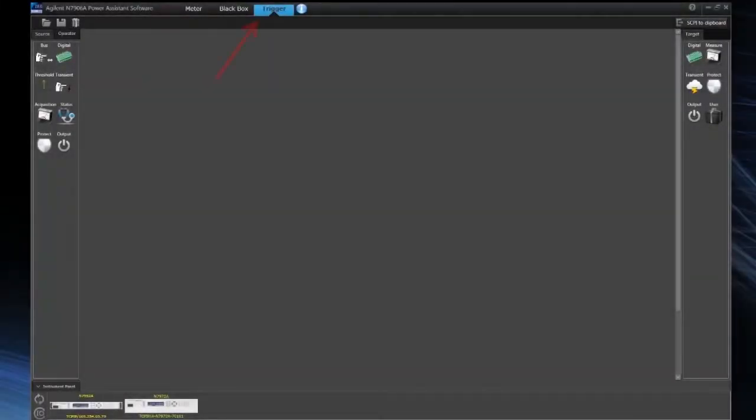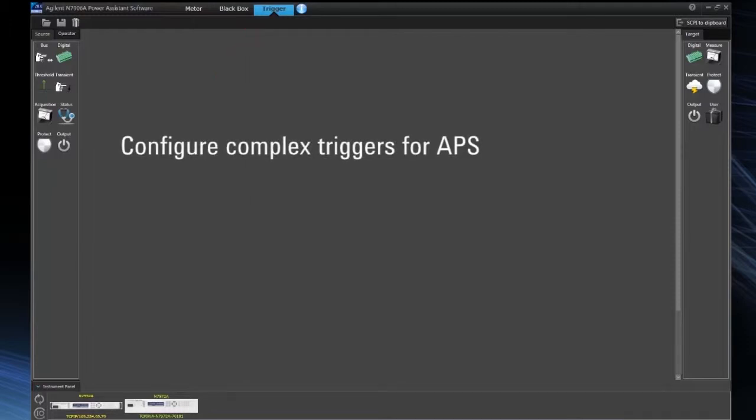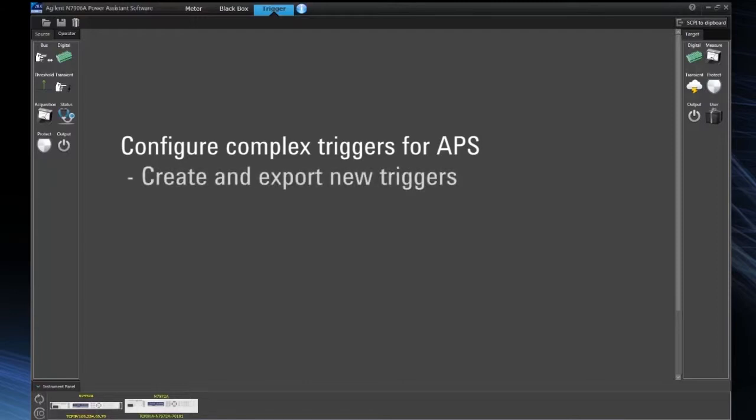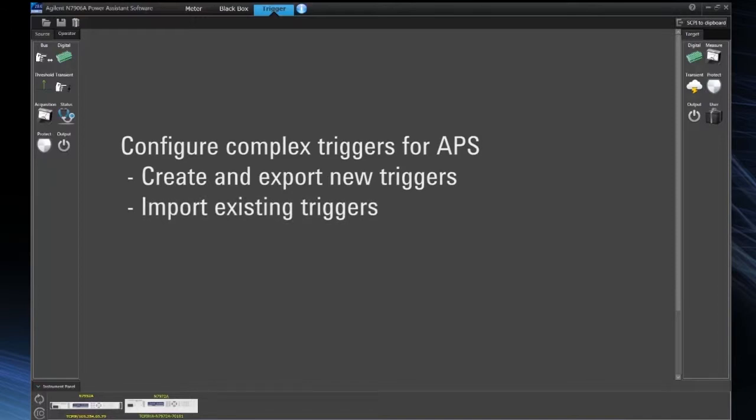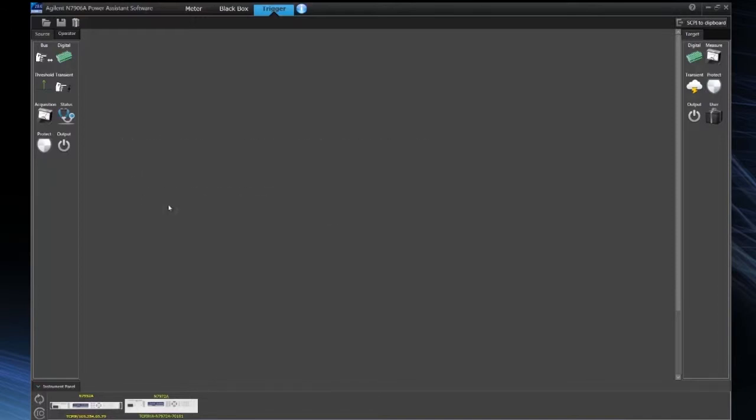Now we're looking at the trigger configuration function of the Power Assistant software. This allows you to configure complex triggers for the Advanced Power System power supplies. So you can not only create them and export them to the instrument, you can also import existing ones from the instrument into the software.